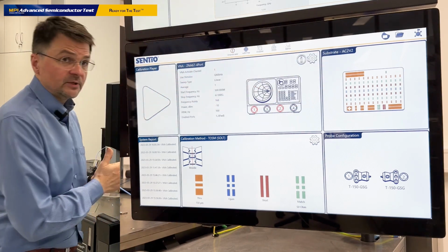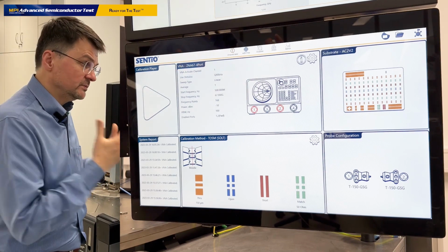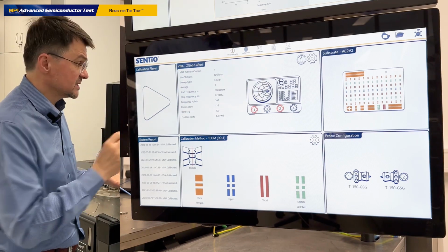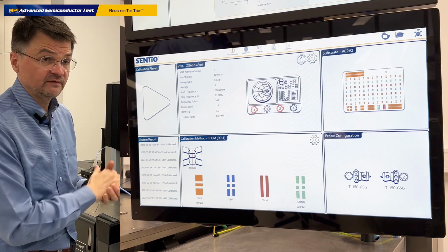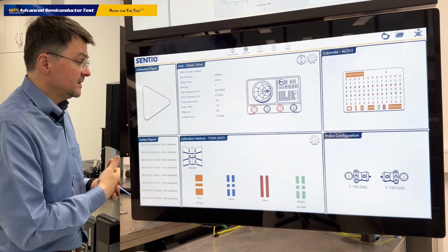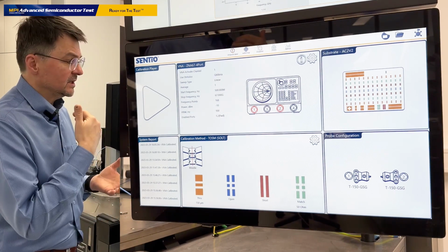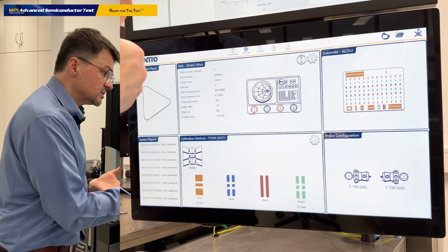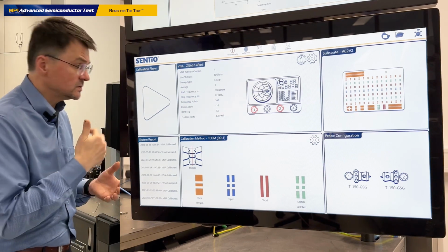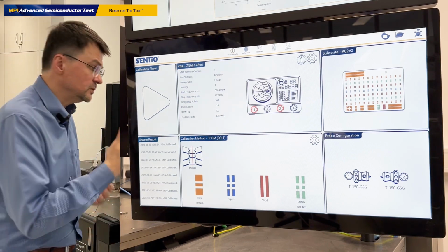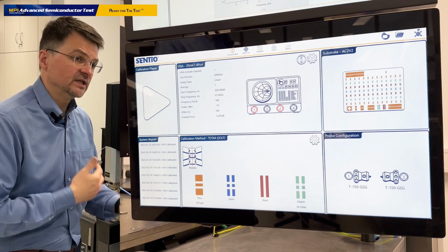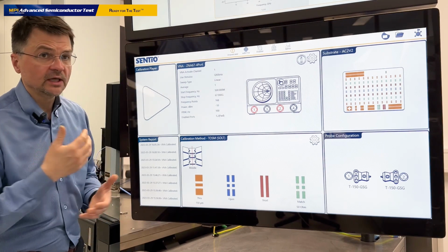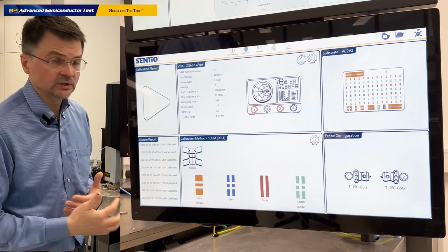If you don't have calibration software, an operator of the machine must key in all these parameters into the network analyzer graphical user interface and create the cal kit. This is not only a tedious task. Some parameters are not possible to enter directly for some network analyzers. You need to do the model parameter conversion and recompute what the effective delay of your load standard is, based on the inductance parameters of the load standard and so on.